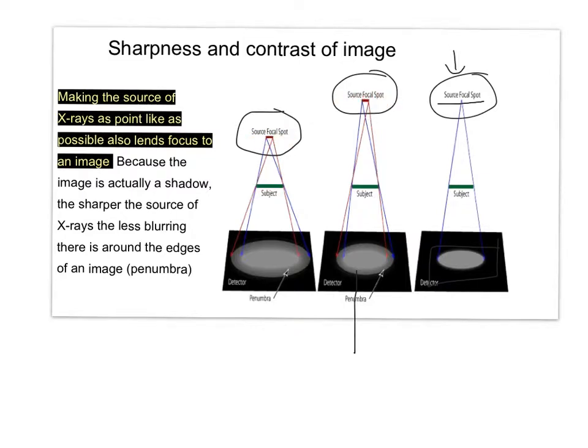Having a wide focus point means that you get light coming from lots of different directions, therefore causing overlaps in the light. So if this is our subject — this is what we're taking a picture of — the light can overlap in varying intensities to cause a shadow. But if you have a really small focal point, then you get a sharp edge because there isn't shadow forming. So making the source of x-rays as point-like as possible lends focus to an image because the image is actually a shadow. The sharper the source of x-rays, the less blurring there is around the edges of the image. So that's going to increase the sharpness of your picture.